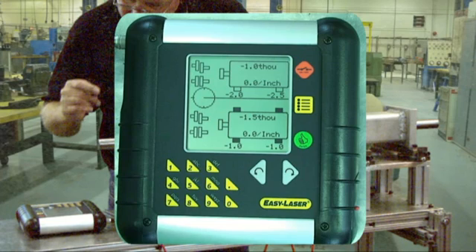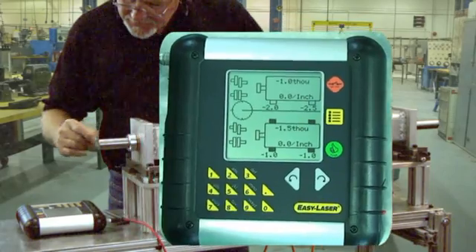The tolerance for a 1725 RPM machine is that 4 thou is acceptable and 2 thou is excellent for offset. With 0.8 thou per inch as acceptable and 0.5 thou per inch as excellent we are well within the excellent range and we did it in one move.